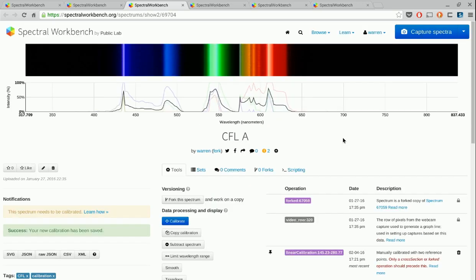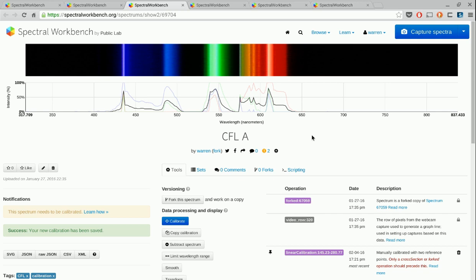Don't worry too much about that. But basically, you know, in the other example where it didn't fit perfectly, things like the lens shape and the diffraction grating shape might make it so that two points aren't quite enough to get a perfect fit. You might have to stretch different parts in different amounts. We're not going to deal with that just yet, but in the future, we might be able to do an even better calibration. We'll call it something different. So for now, linear calibration will show here. And if you refresh the page, it won't say that it needs to be calibrated anymore, which is pretty good.